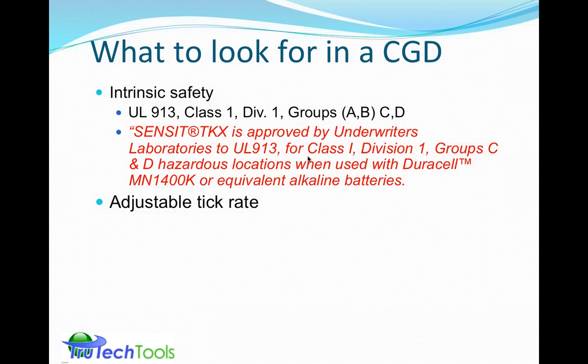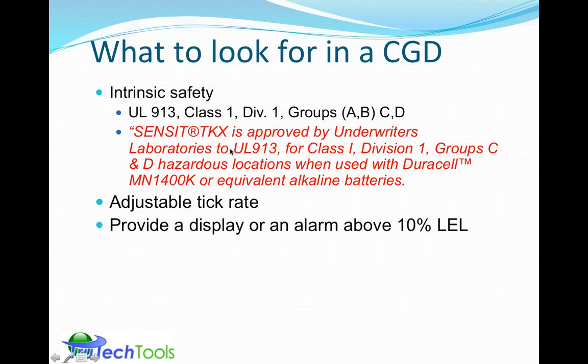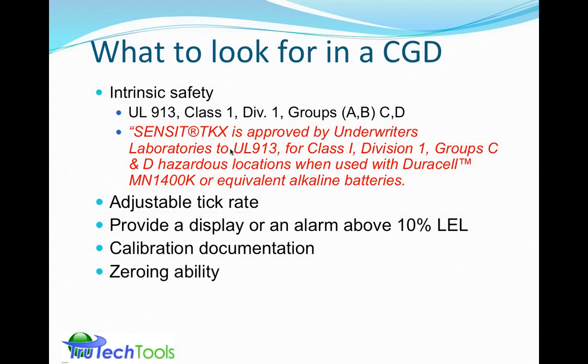You're also looking for an adjustable or variable tick rate. Again, going back to that note, which I'll check again. And then providing a display or an alarm above 10% LEL. A calibration documentation, quote unquote documentation, some traceability, and the ability to zero the device. So these are the main things you're looking for.